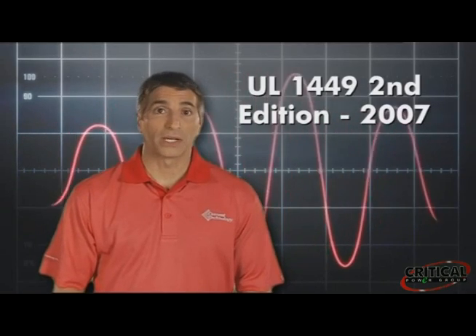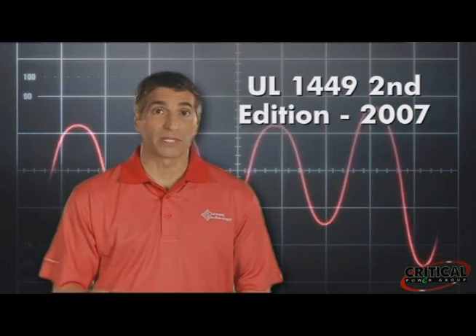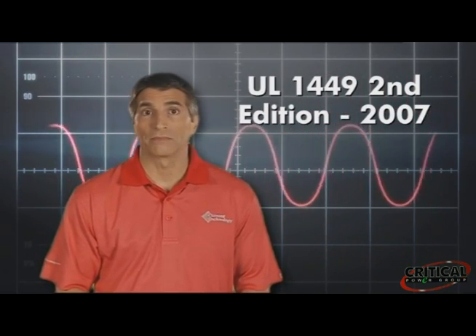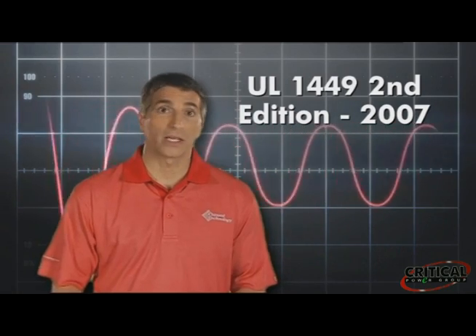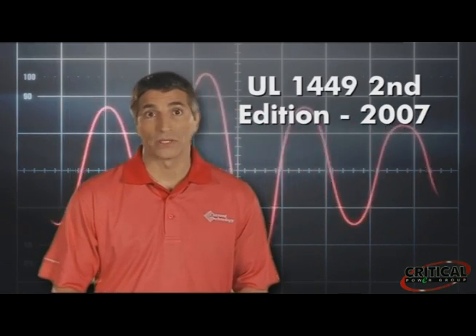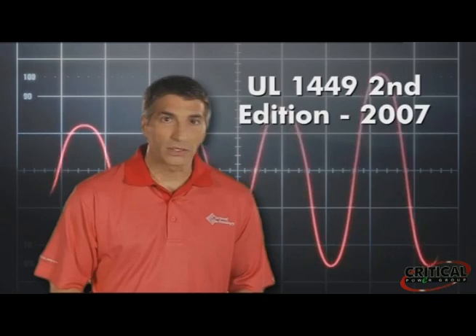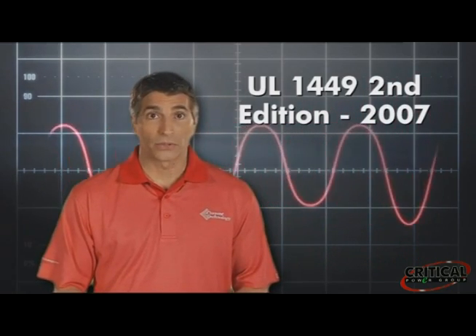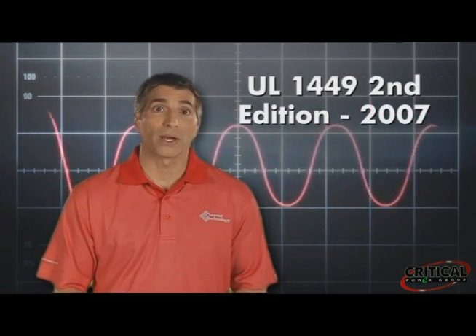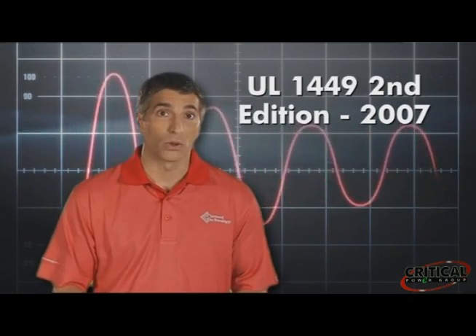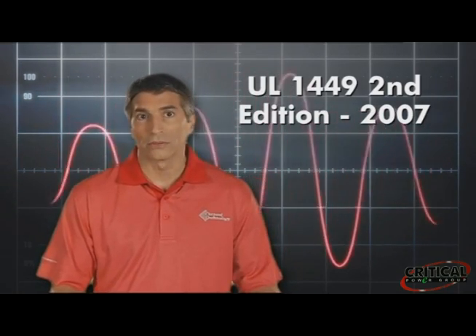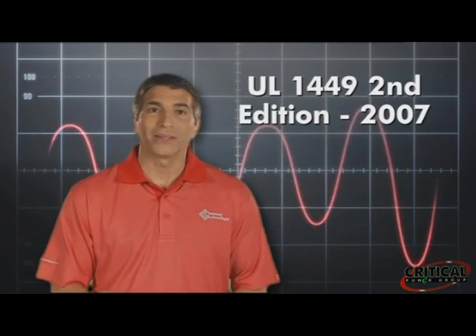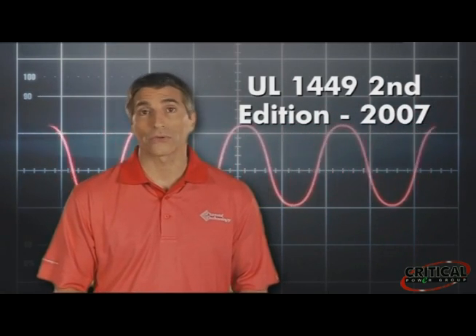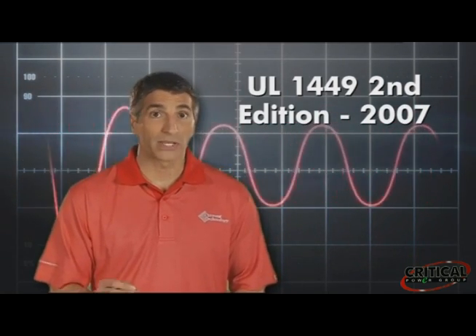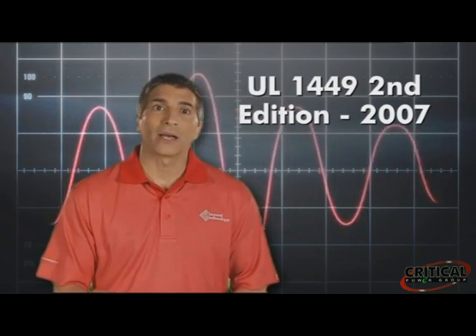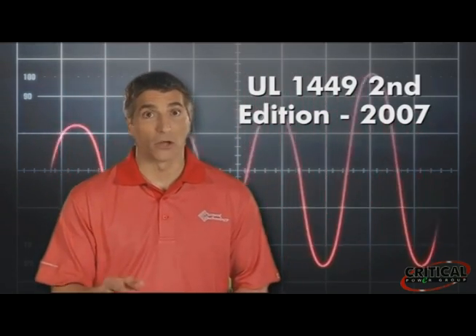UL 1449 states that all SPDs must be designed so that the SPD fails safely. It must have a mechanism that takes the SPD safely offline before the MOVs fail. As a consequence, other SPD manufacturers that use only MOVs have designed their products so that they're now less robust than they were. They're taken offline sooner, which makes them safer, but the SPD is no longer protecting the electrical system. CAPS, with its hybrid selenium design, stays online much longer, protecting your system longer.